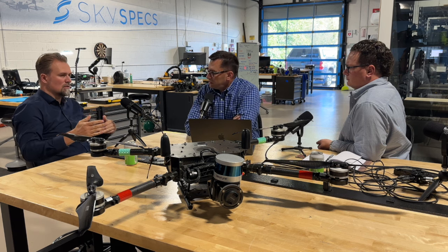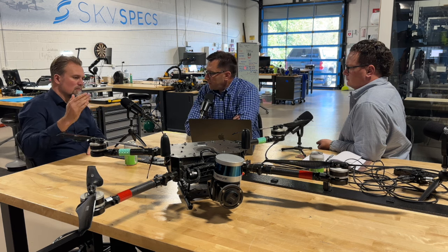You want to do two things. You want to avoid risk. Obviously, you want to avoid those costs. And on the liabilities, when I say liabilities, I mean all your known repair tasks that are in the future. Let's say you have 2 gearbox repairs that are pending. Why not do it at the same time? So you only have to get the crane out to site one time, right? Then you optimize your liabilities. So there's optimizing your liabilities and avoiding your risks.